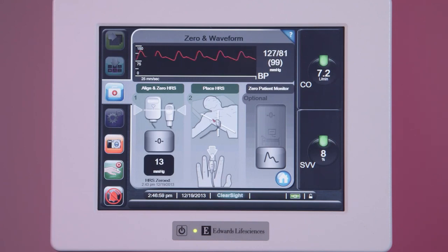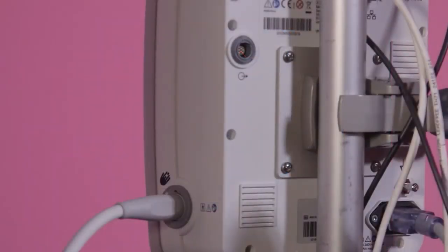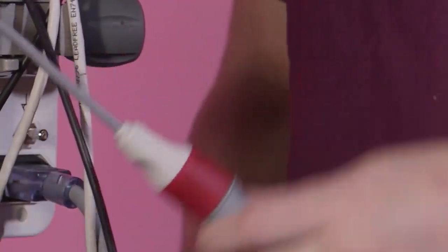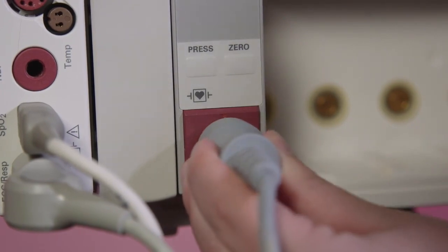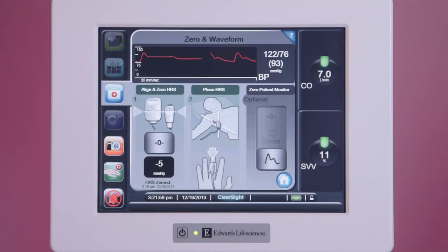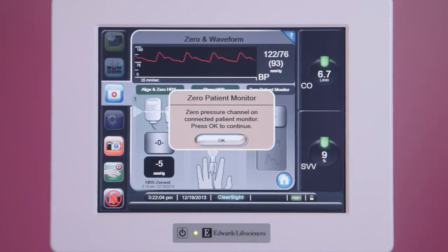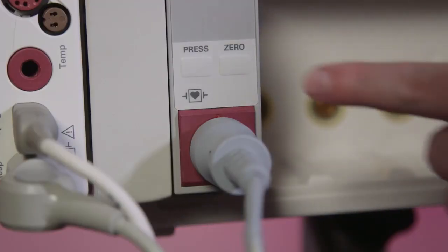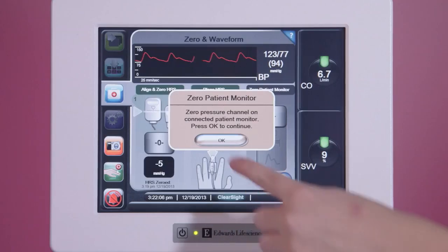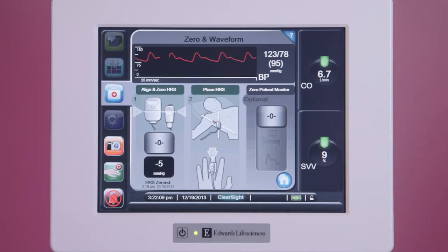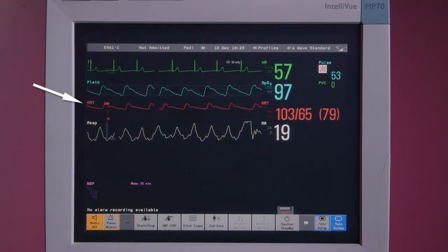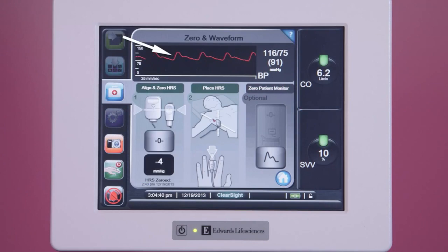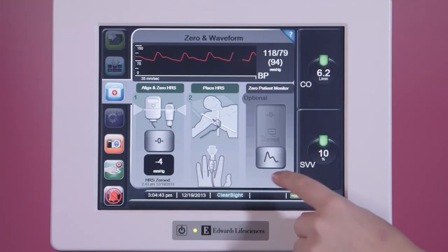To display continuous blood pressure on a patient monitor, connect the patient monitor adapter cable to the pump unit and patient monitor pressure cable. Connect the pressure cable to the patient monitor. On the zero and waveform screen, move the pressure output selection to the zero position. Zero the arterial pressure channel on the patient monitor. Move the pressure output selection to the signal position. Confirm the arterial pressure waveform is displayed on both the patient monitor and the EV1000 clinical platform. To exit the screen, tap the Home button.